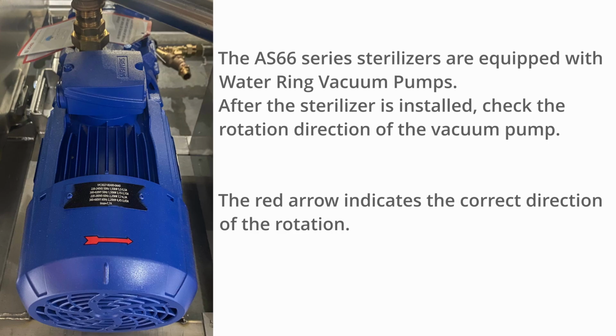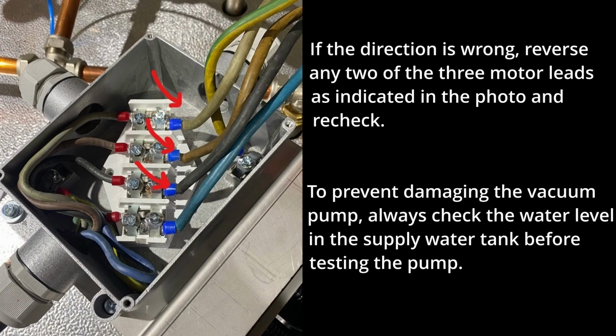The AS-66 series sterilizers are equipped with water ring vacuum pumps. After the sterilizer is installed, check the rotation direction of the vacuum pump. The red arrow indicates the correct direction of the rotation. If the direction is wrong, reverse any 2 of the 3 motor leads as indicated in the photo and recheck. To prevent damaging the vacuum pump, always check the water level in the supply water tank before testing the pump.